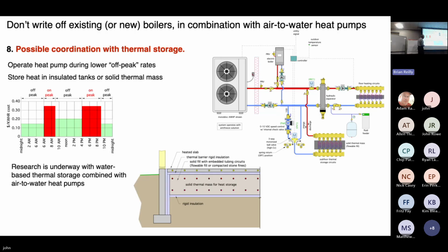And this is just a concept right here. This would be solid thermal storage. And I don't want to go too far into it, but the idea would be there'd be a material, and it's probably not going to be concrete. It's going to be something called flowable fill that would be in an insulated compartment, if you will, under a floor slab. And it's critical that there's insulation between the floor slab and this thermal mass, because you need to control the rate of heat release.